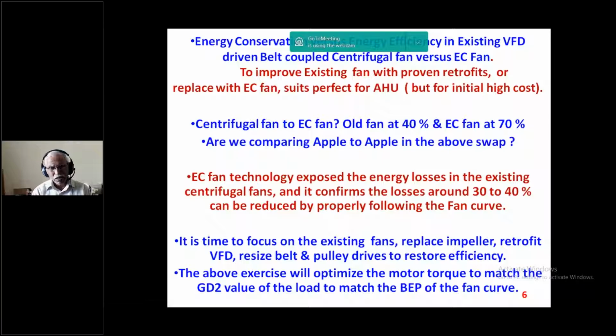There are two schools of thought here. The energy conservation aspect for a given industry asks: on the existing fan, what can be done? Replacing the impeller, retrofitting a VFD, or resizing the pulleys and belts. In these areas we can achieve almost 30 to 40%. Whereas some industries, the green building industries, go straight away for EC fans. This existing retrofit or replacement of subsystems will cost less than a lakh, while an EC fan replacement costs more than 4 lakhs. The initial cost is very much more. It is a total replacement.